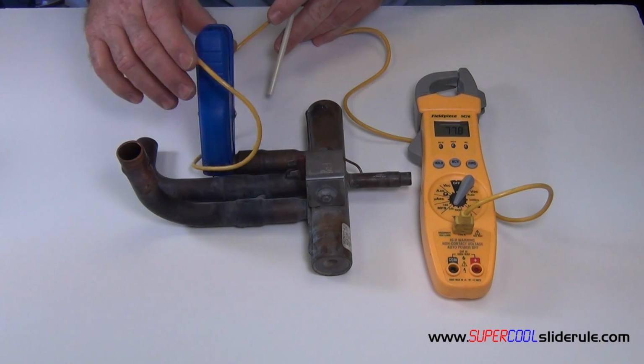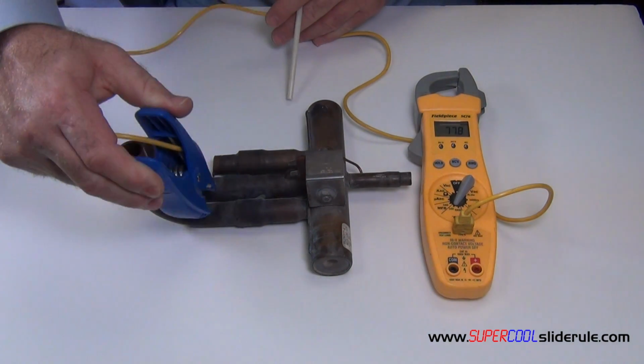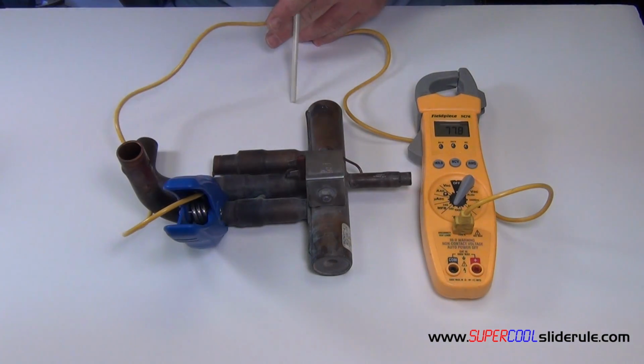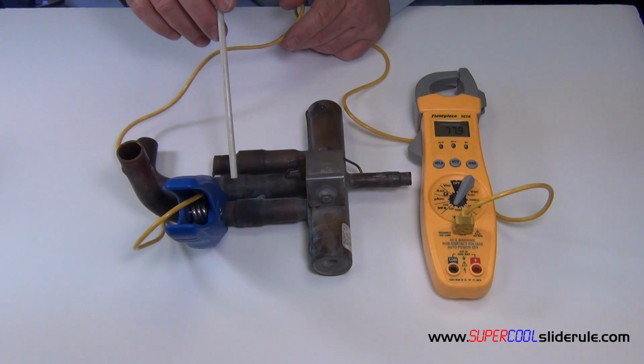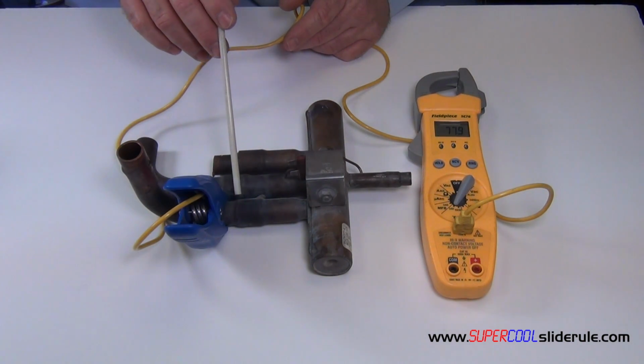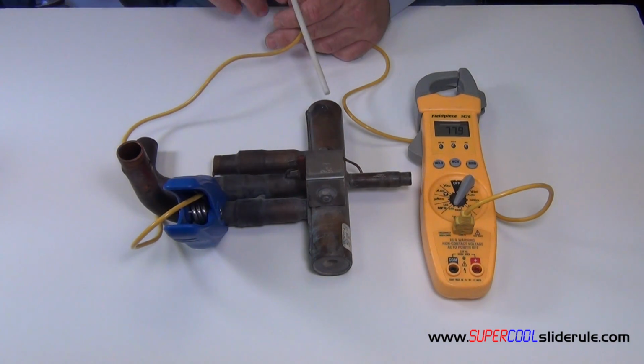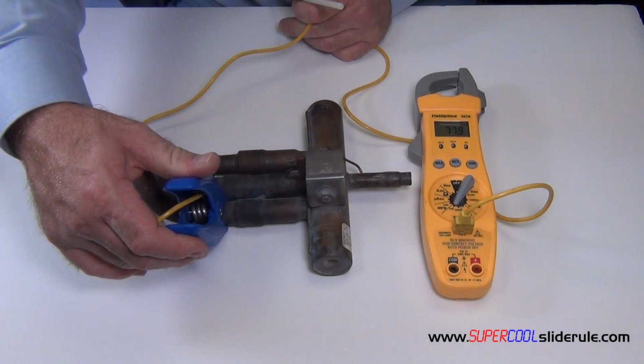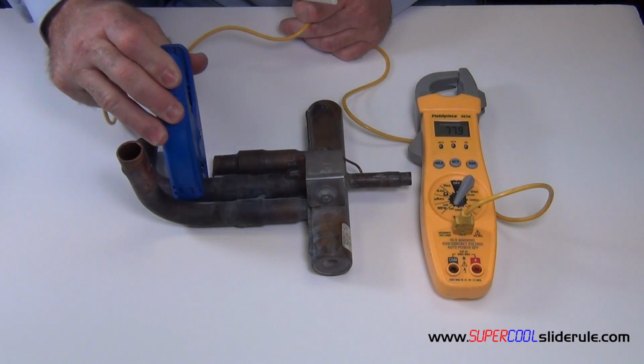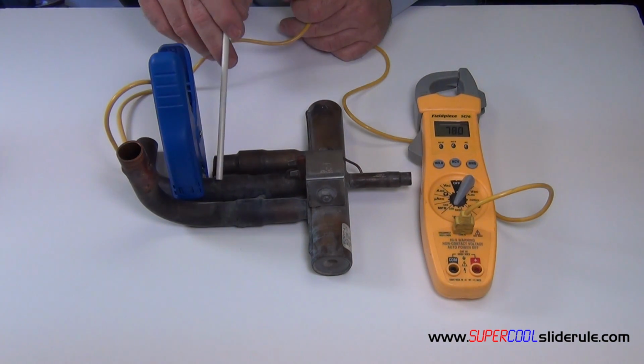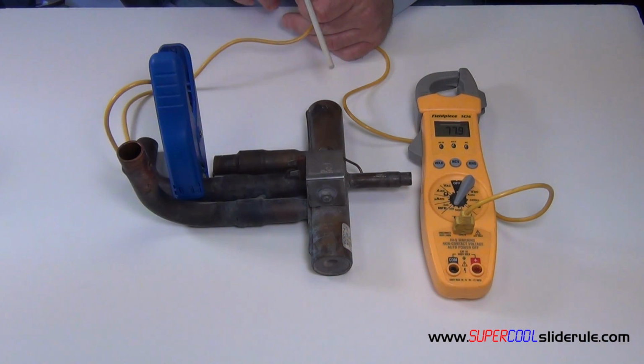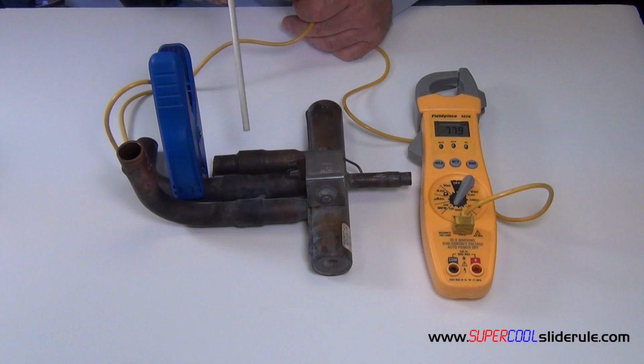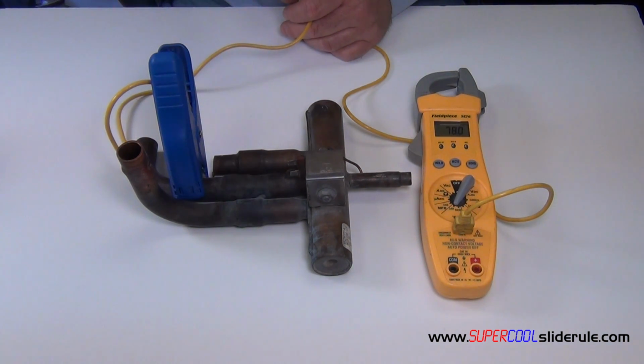Once we've established that, we check the other two tubes. Once again, we are looking for a temperature swing of no more than 5 degrees. So if the temperature on this one is, let's say, 50 degrees, the temperature on this one would need to be 45 to 55 degrees. If the temperature differential is larger than 5 degrees, most likely you have a bad reversing valve.